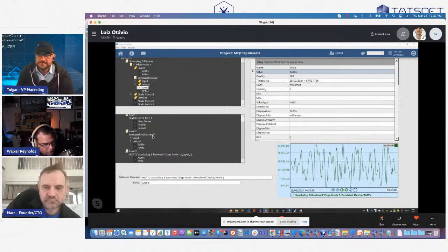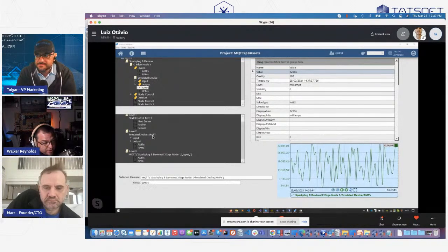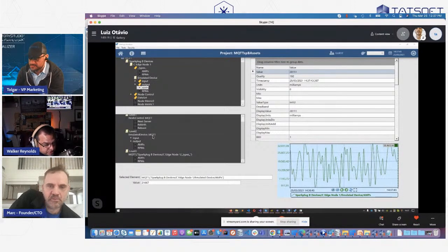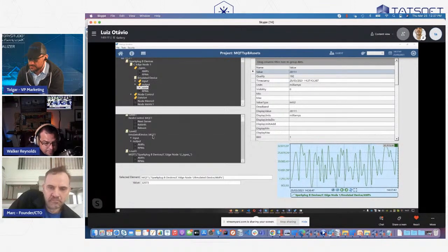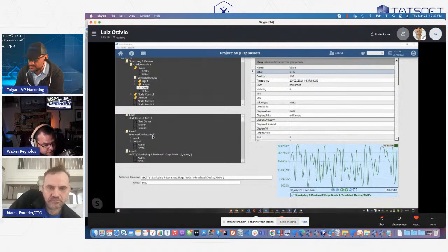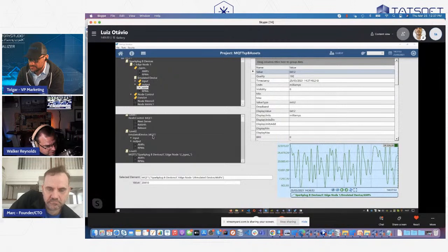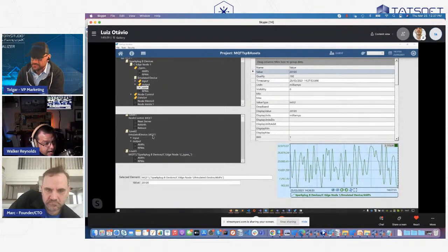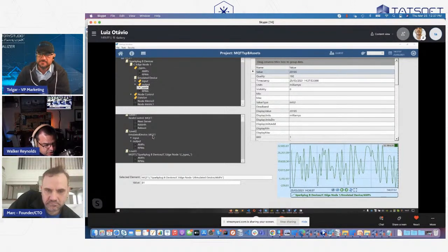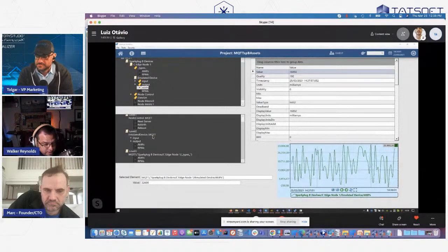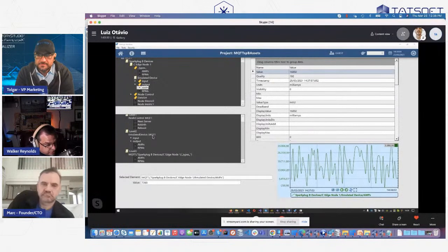I could create one visualization that reacts to whether or not those sensors exist. So on line 1, I've got all 4 sensors, therefore my visualization contains all 4 sensors on the screen. The screen itself reacts to what's in the namespace. On the second line, the exact same screen only sees 3 of the sensors: level, temperature, and flow. So pH does not show up on the screen.